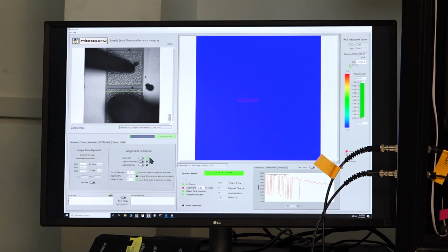We'll wait for the button to turn green. Then we again select capture reference. As I have discussed, for capture reference we have to select a region with features like edges, spots, and so on. So we select the same region and click on capture reference. With this in place, we'll set the alignment percentage to 97%, because we see that the alignment score is quite good, 98% it is showing. The vibration filter is kept at 10. It should be kept as low as possible, as discussed.